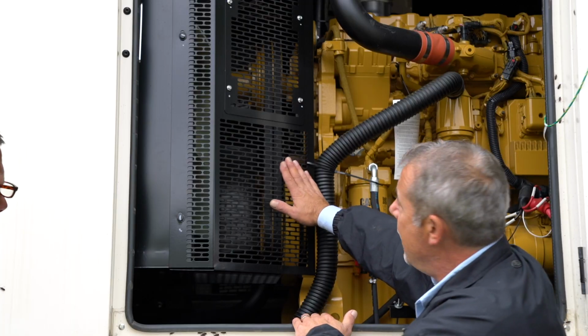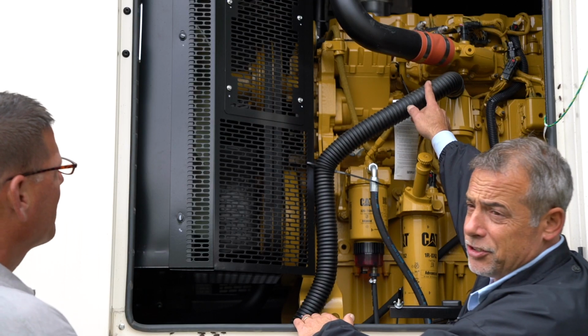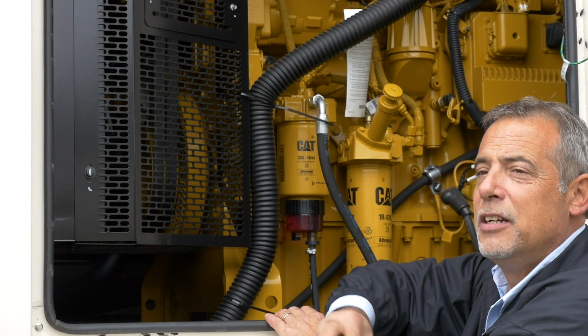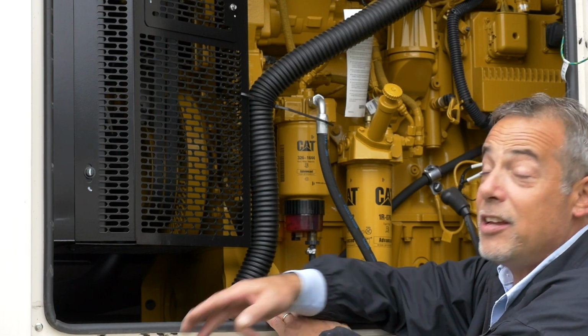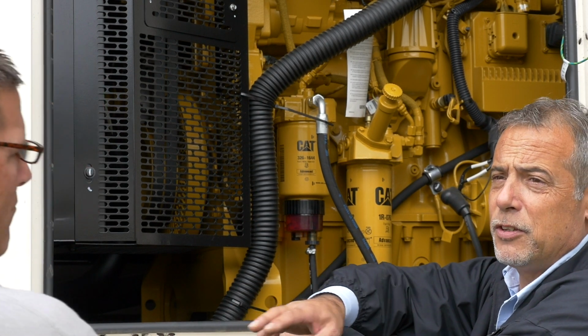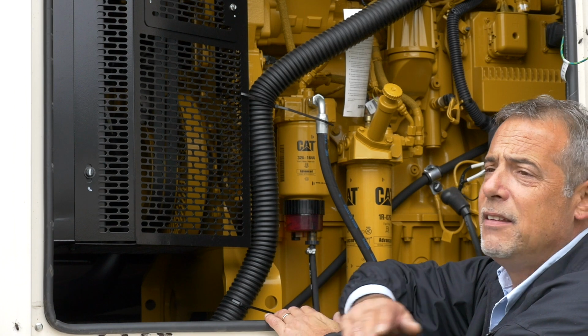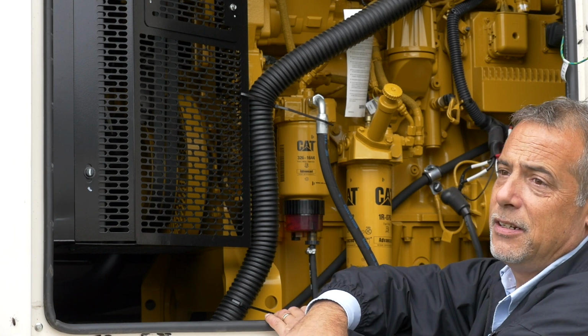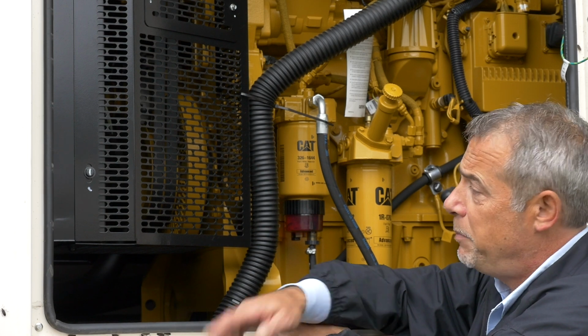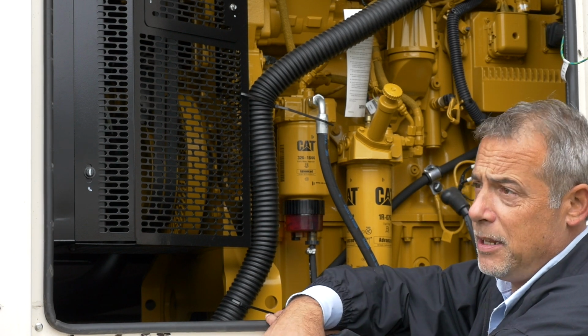Fan belts, hoses, and batteries: 3 years. Whether they look good, they test good, everything's plastic and rubber. They're going to dry rot, you can't see if they're bad. We tell you just change it. If you want an emergency generator, you got to make sure it's ready at all times. Especially with the hoses and the belts.